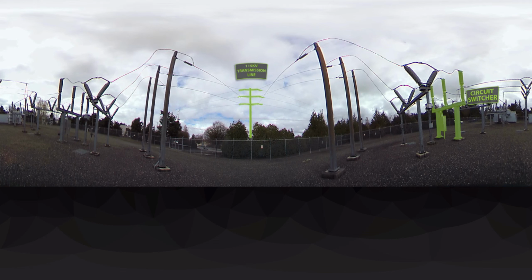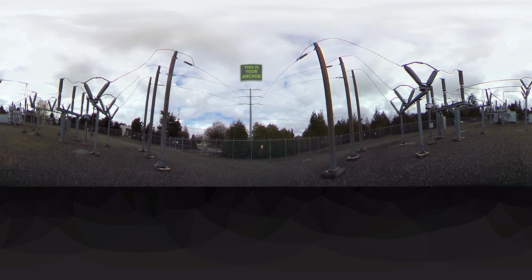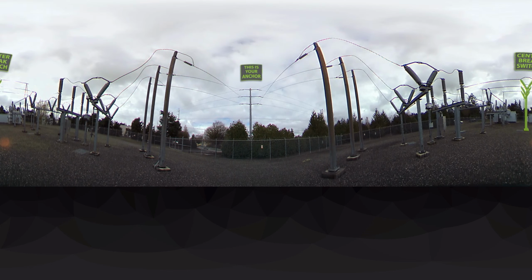Now, if your camera is centered on the 115 kV anchor point, if you rotate your camera 180 degrees, directly behind you, you can see where both halves of the substation connect in the center. The device located there is another V-break center switch. This particular V-break center switch acts when necessary to completely isolate both high sides of the substation. But when it's closed, it combines the 115 kV lines into a single circuit.